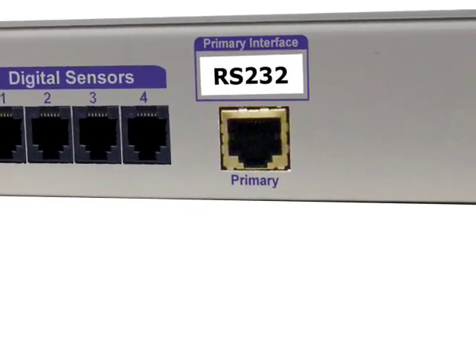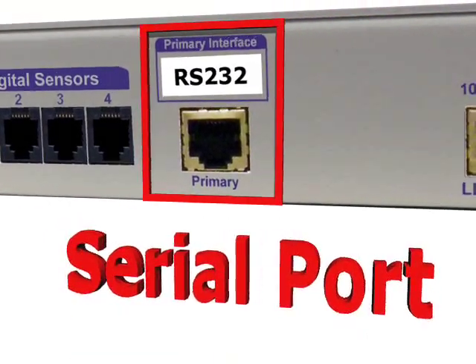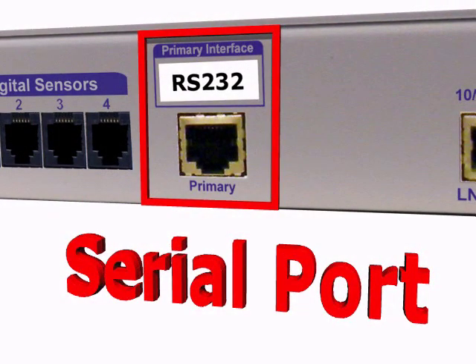Next to the D-wire ports is a serial interface that can be configured depending on what your needs are. In this case, it's been configured to be an RS-232 serial port. This can be used to poll the unit, but more commonly it's used as a terminal server to reach out and control a piece of legacy serial gear that you ordinarily couldn't reach over LAN.